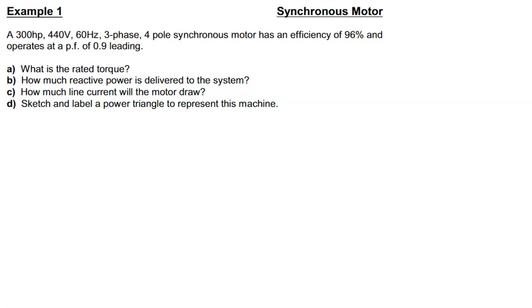And so we'll start now by thinking about the rated torque. And when I ask you for rated torque, it's not torque developed you're going to calculate, but torque output. And the reason for that is P out is the value you have instead of a mechanical power developed by the machine. And so P out is 300 horsepower.